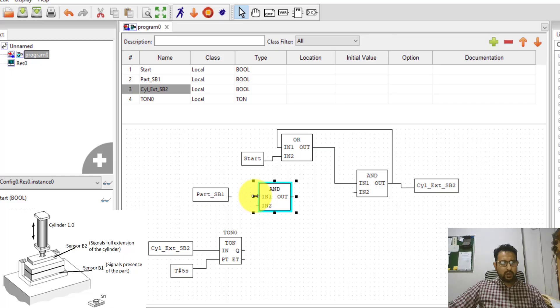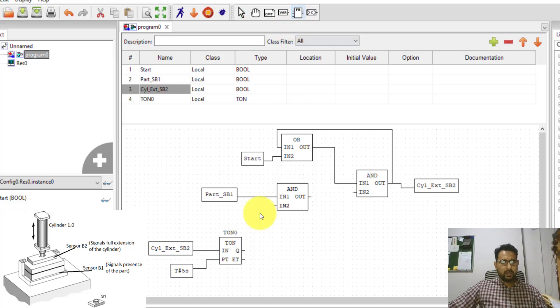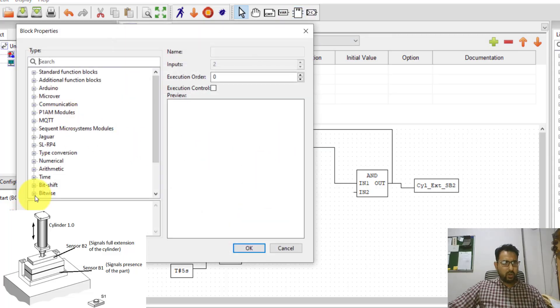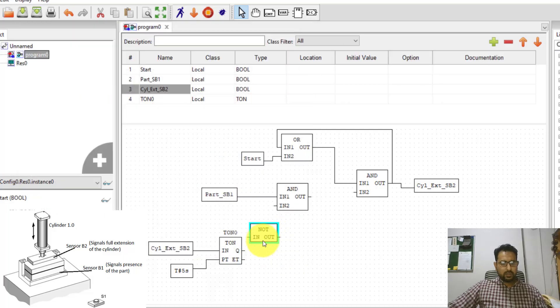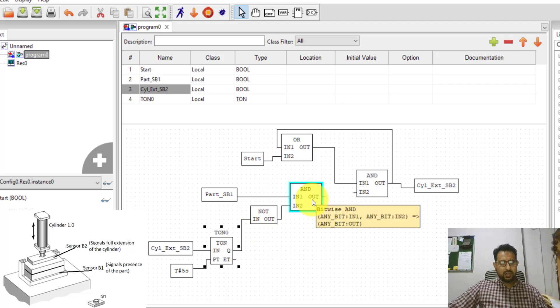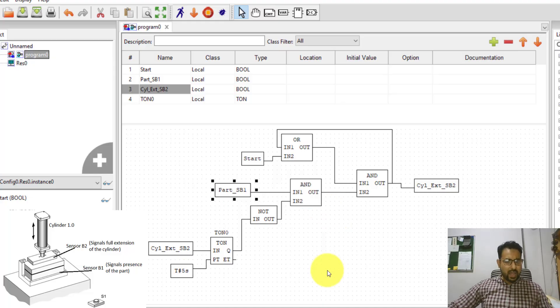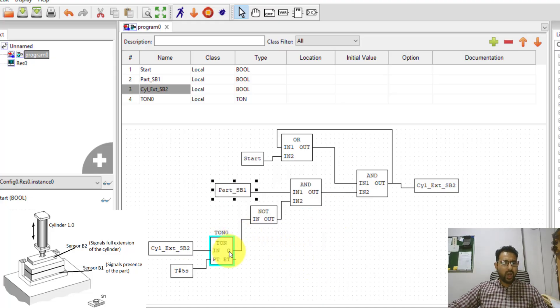This AND block checks whether the part is present and the timer is not done. I need a NOT gate for that — I'll use the NOT gate from the bitwise section. So if the part is present and the timer is not done, the output will be on. Once the timer completes, the Q pin goes high, the NOT output goes low, the AND output goes low, and the cylinder turns off.